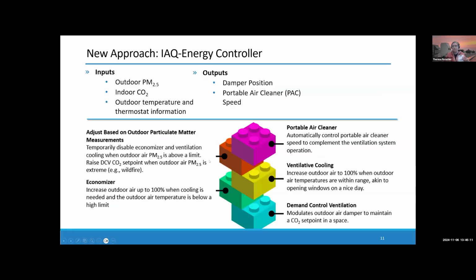And so this is my proposed better way, which I've called the IAQ energy controller. Like economizers and DCV was all developed as an energy saving tool, but now we want to think about both energy and indoor air quality. And so the inputs to this system are the outdoor PM 2.5 levels, the indoor carbon dioxide, and you need the outdoor temperature and the thermostat information, which you would already have in a basic control system. And we're going to output a damper position.